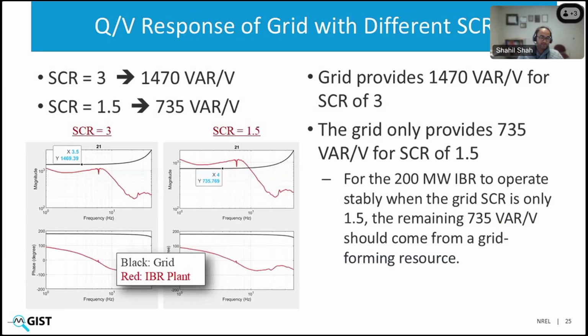And this is through a very simple equation that you can find in some of the publications whose link I have provided in the previous slide. What it shows is that if there is a grid with SCR of 3, if there is a 1 volt change at the terminal at the POI, that grid will automatically dispatch 1470 VAR per volt very fast, in the transient to sub-transient timescale, basically 4 to 40 hertz.